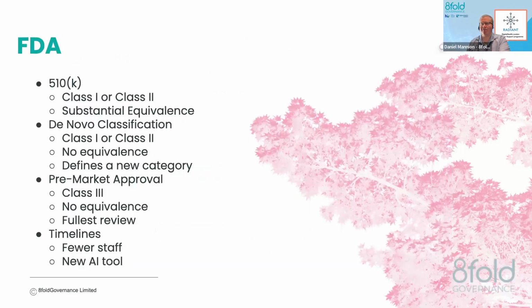The FDA have 3 different methods. 3 is an understatement. 3 most common methods for approval. 510K is proving that you're equivalent to a product that's already on the US market. De novo classification is when you've got a new product, but you don't think it's as risky as a Class 3 product, and you want to ask them to give you a Class 1 or Class 2 classification. And it creates a new one of those 1700 rules I was talking about earlier.